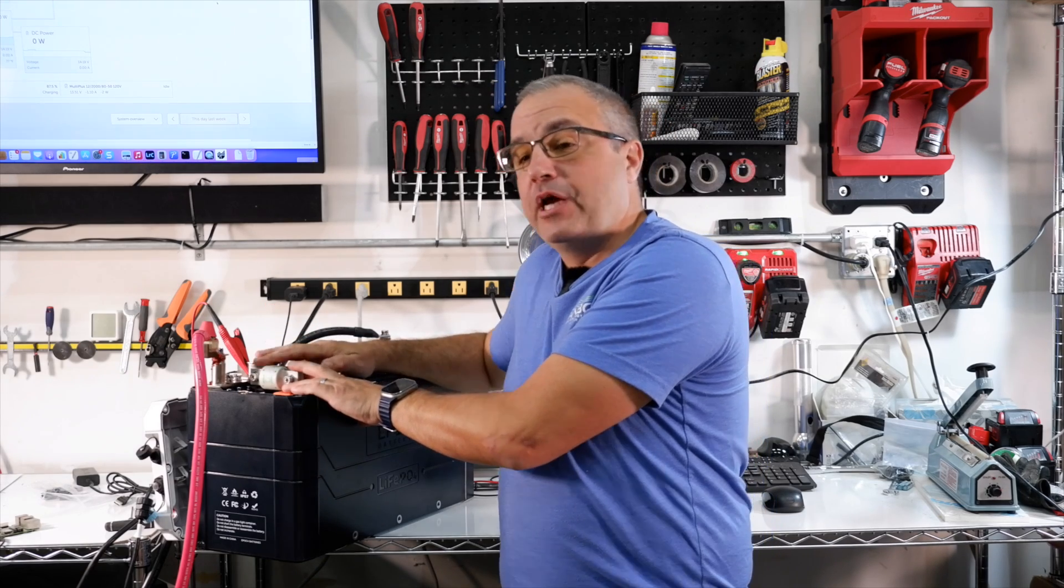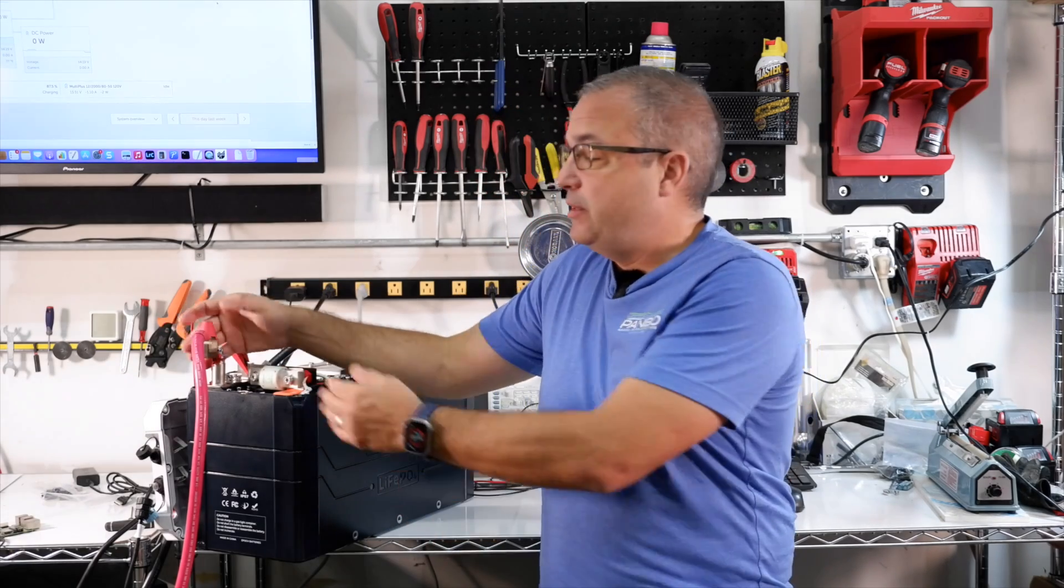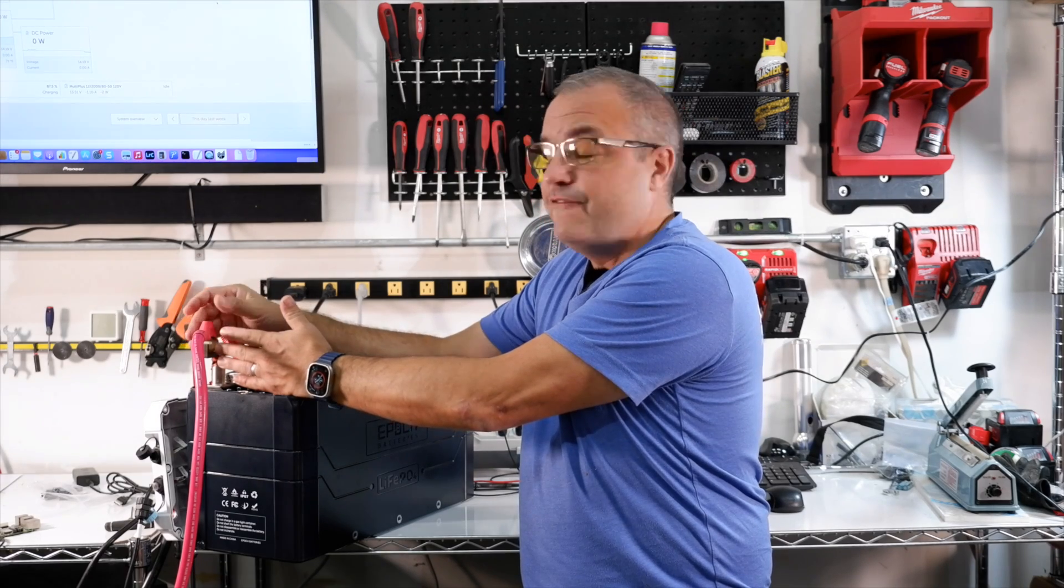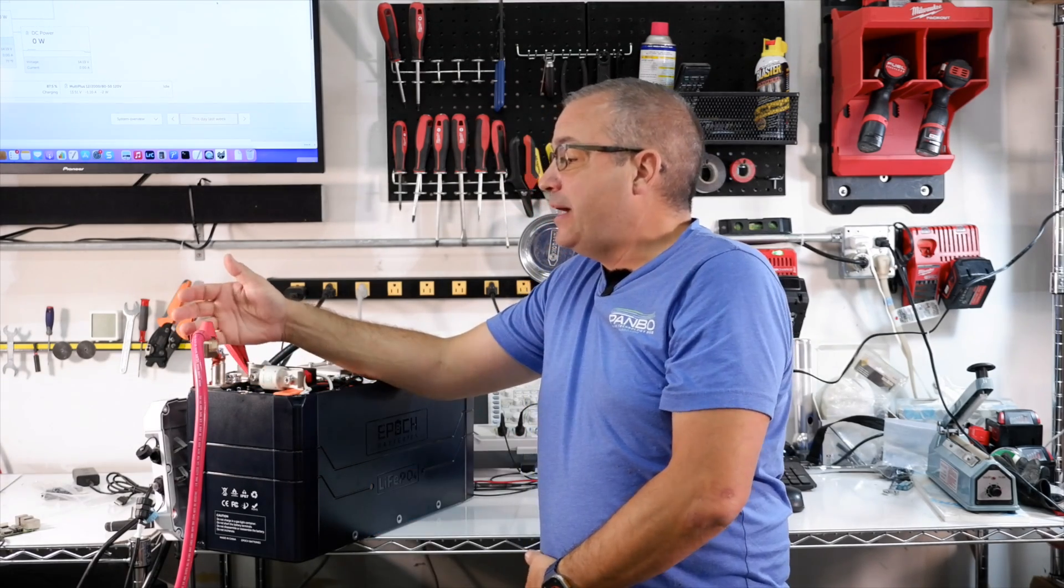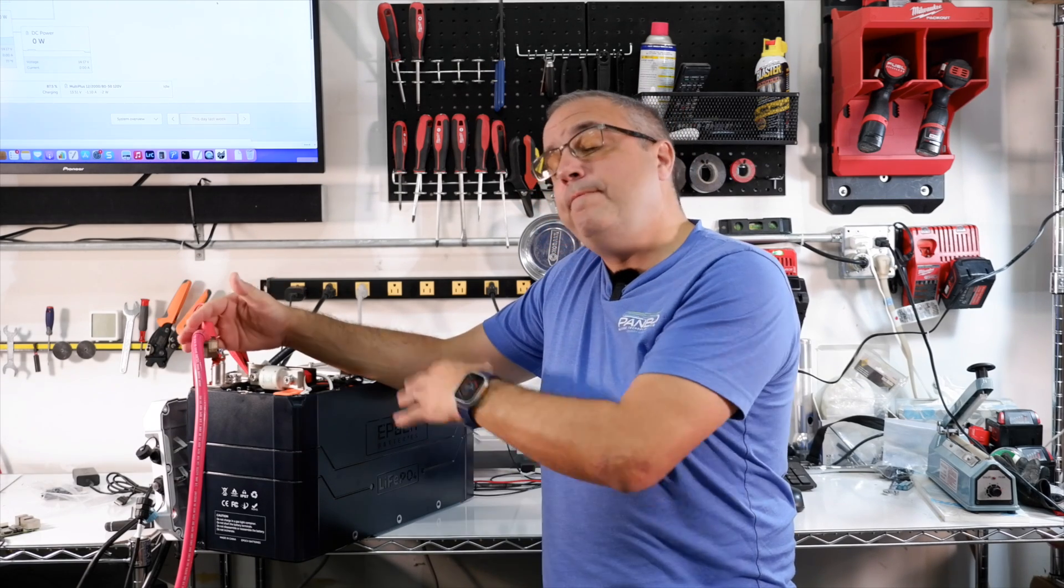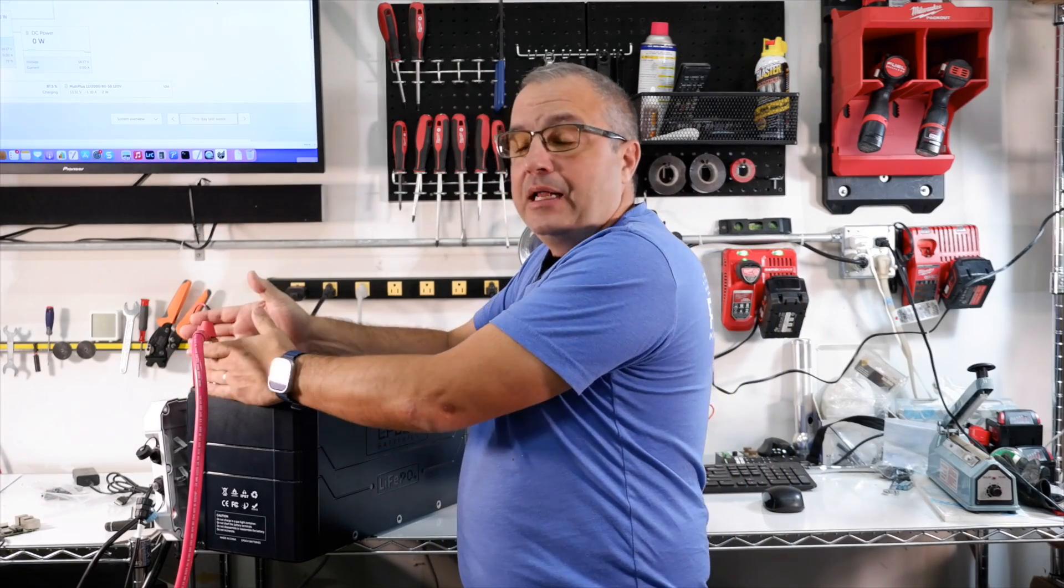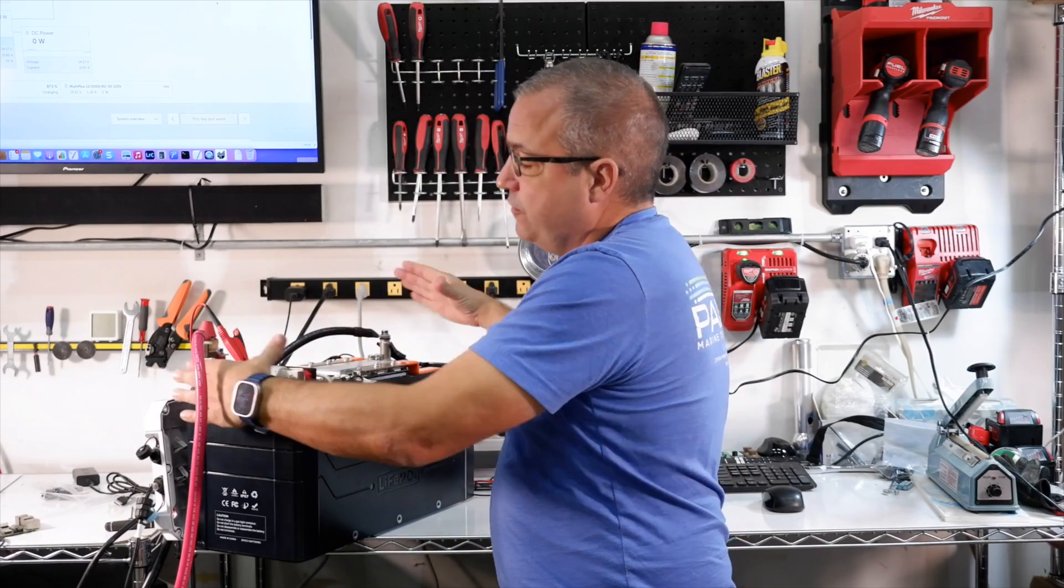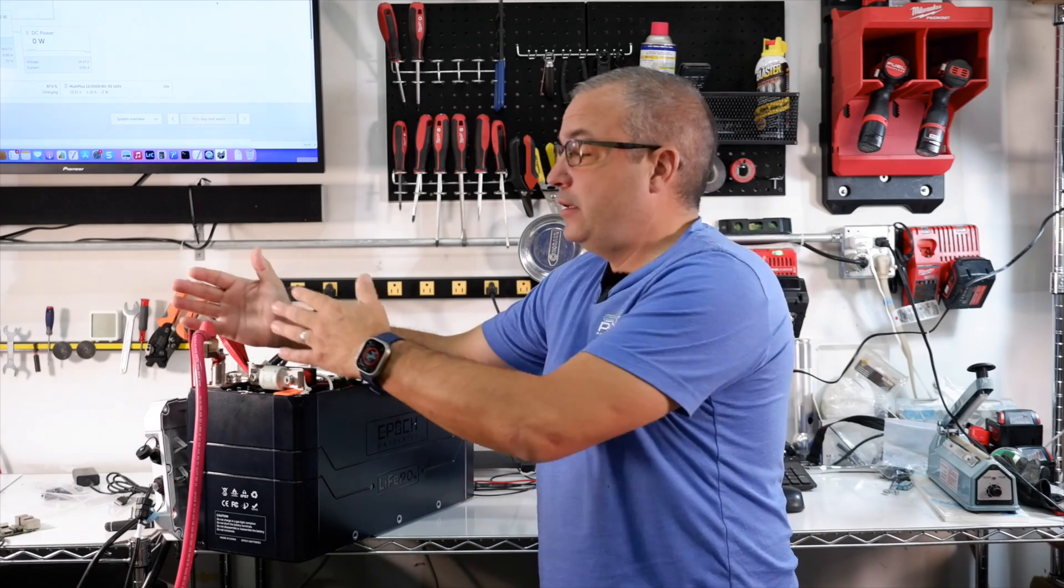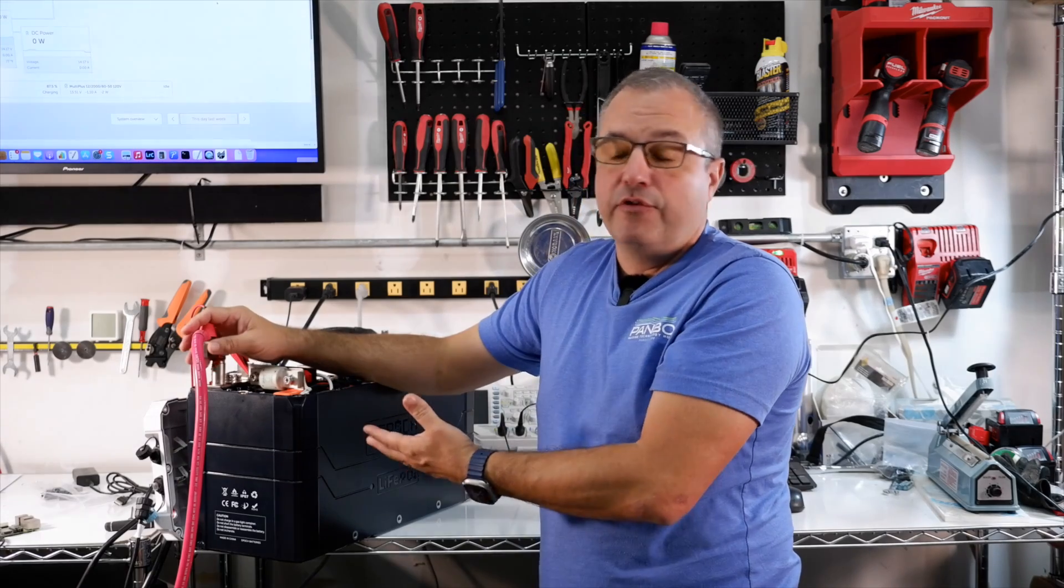So our next over current protection doesn't need to meet that 20,000 amp AIC. And so you can use something like what I'm using here. This is a 300 amp MRBF rated with a 10,000 amp AIC. Wouldn't be enough to be the primary fuse, but it's a great secondary fuse safely mounted on top of the battery. Ordinarily the battery would be closed with the case on top and the MRBF right here. And now you've got all of your fusing easily accessible, safely mounted, and meeting all of the various requirements.